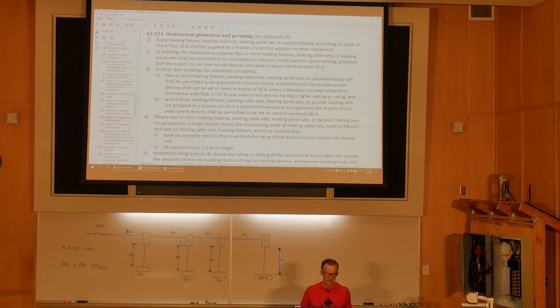All right. 62-114, subrule 1. Every heating fixture, heating cable set, heating panel set, or parallel heating set having an input of more than 30 amps shall be supplied by a branch circuit that supplies no other equipment. Just a statement there. Subrule 2. In buildings for residential occupancy, 2 or more heating fixtures, heating cable sets, or heating panel sets shall be permitted to be connected to a branch circuit used for space heating, provided that the branch circuit overcurrent devices are rated or set at not more than 30 amps.